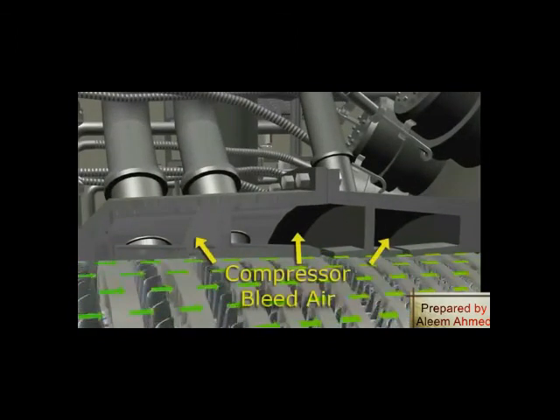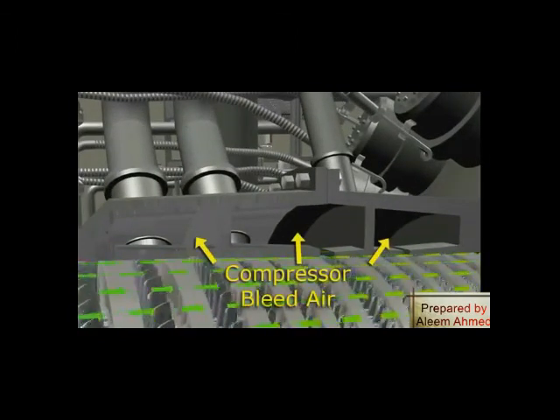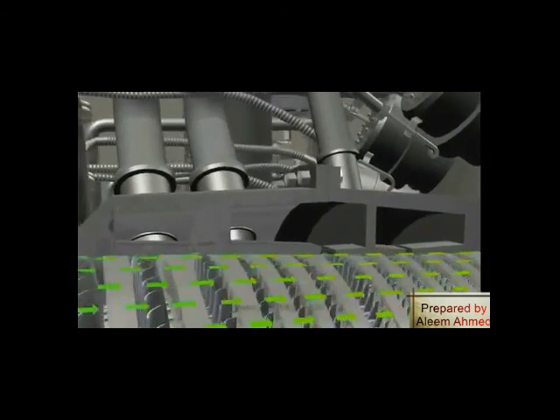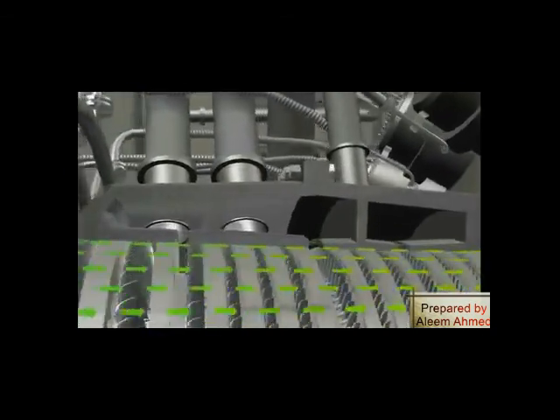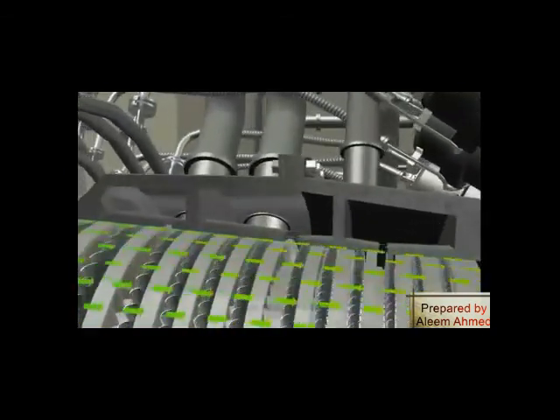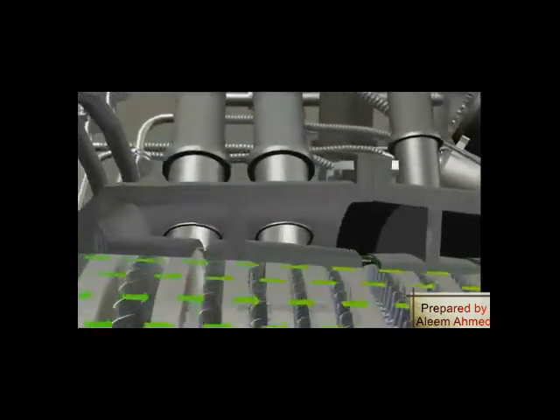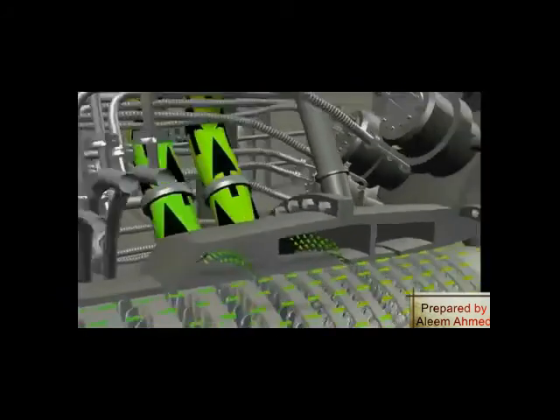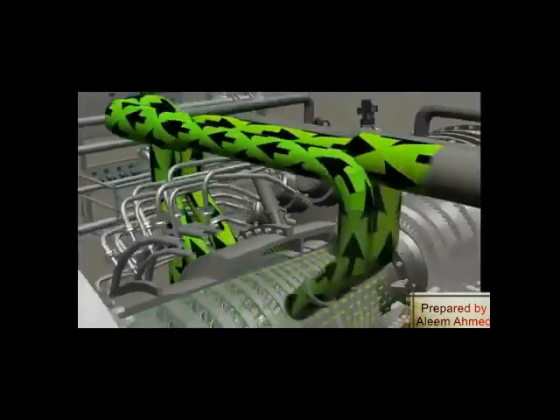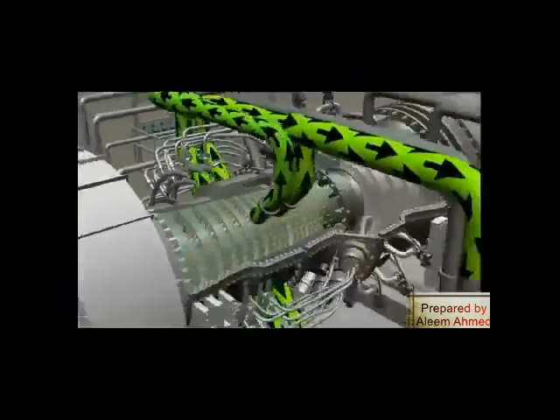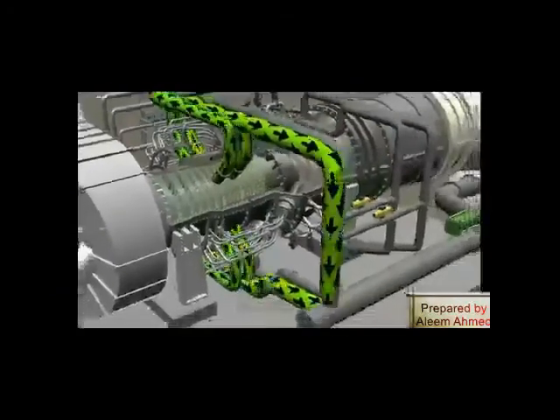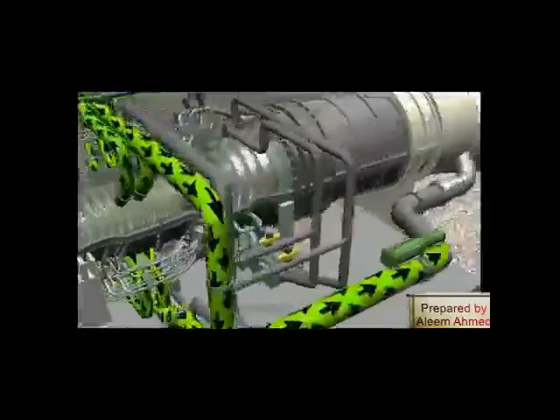Stages nine and thirteen of the compressor serve several unique purposes. During startup of the CT, these stages are bled off to the turbine exhaust via the compressor bleed valves for compressor surge protection.